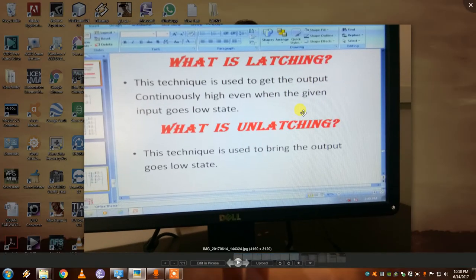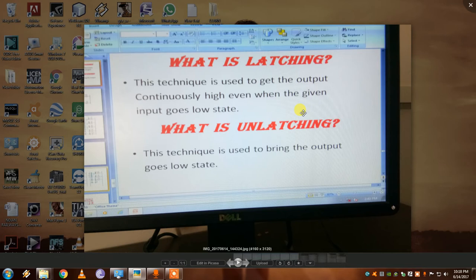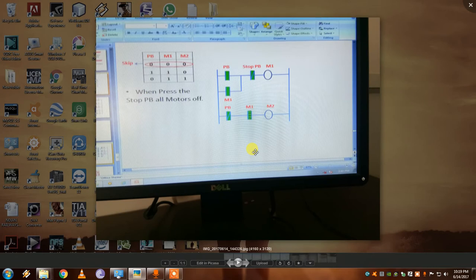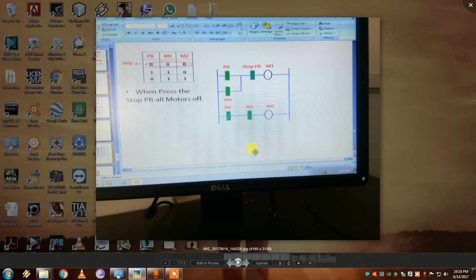Let's go into the software, but before that I need to cover a concept called latching. Latching is a technique used to keep the output continuously high even when the given input goes low. Simply put, if the input is on, the output will be on, and even after the input turns off, the output should remain on. Unlatching is the opposite — another switch is used to cut off the output.